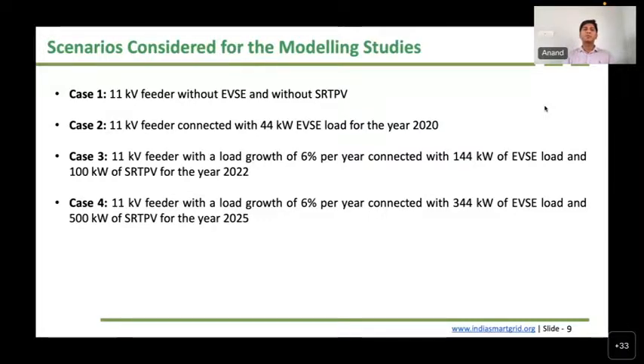The second case added 44 kilowatt of EV load. The third case, on the same feeder, assumed 6% growth per year, with the EV load at 144 kilowatt and 100 kilowatt of solar rooftop coming in.